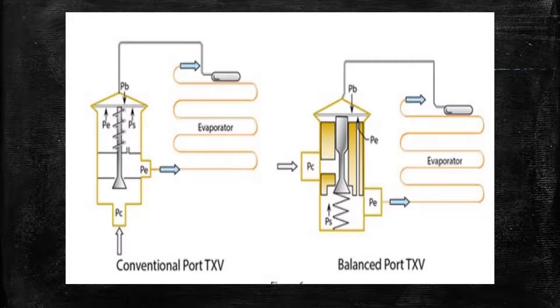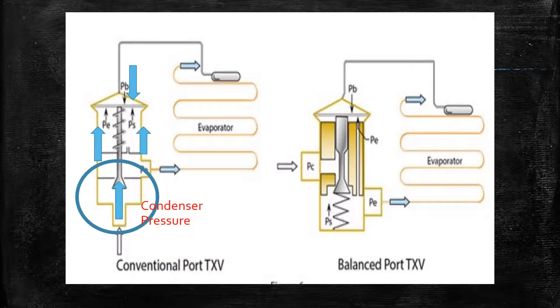In a conventional port TXV we have the evaporator pressure, the spring pressure, and the bulb pressure acting to open and close the valve. We also have condenser pressure which acts upon the metering device to try to open it as the liquid is coming into the valve.